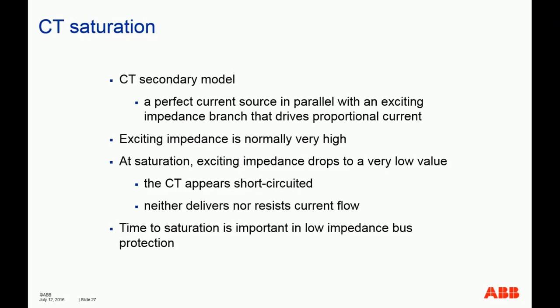Okay. Again, we talked about most of this. We need to emphasize the parameter called time to saturation. The importance of time to saturation is that when you specify a CT properly, every CT would saturate, but if you specify it properly, according to the load, the short circuit level, and the X over R ratio, like we mentioned before, then this CT shouldn't saturate right away. It should at least give you a couple milliseconds or even a cycle for the relay to properly measure an accurate replica of the primary current in order for the relay's differential algorithm to operate.